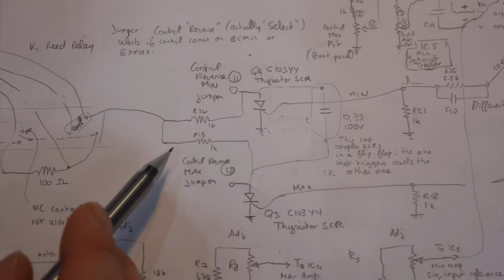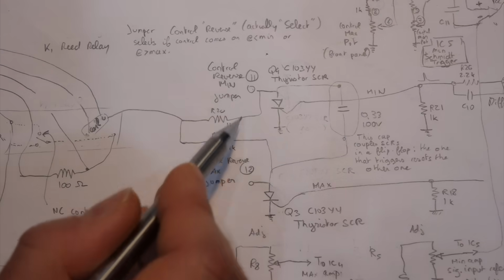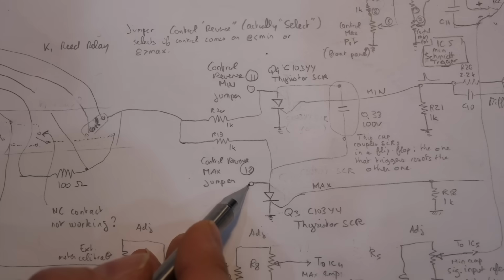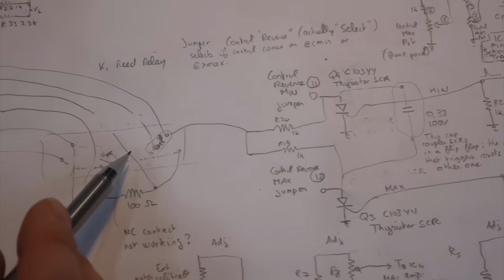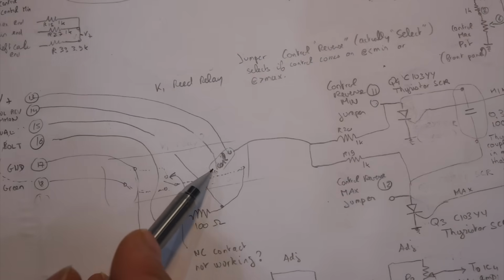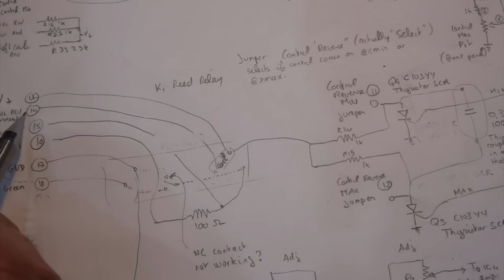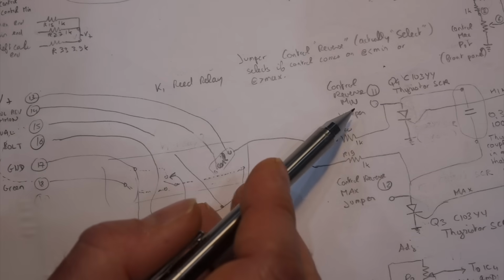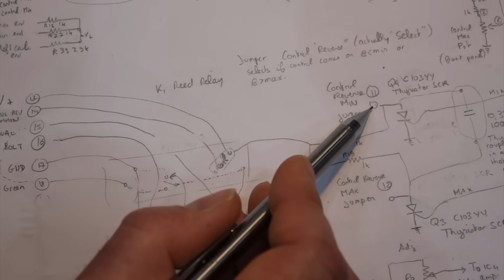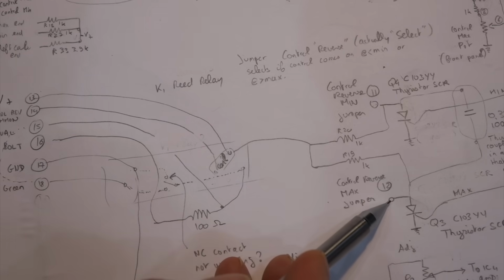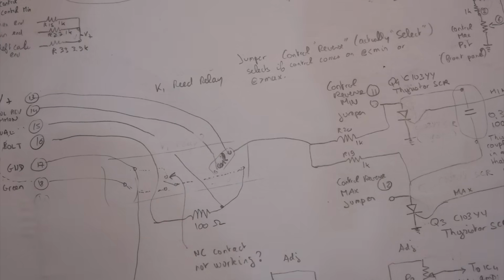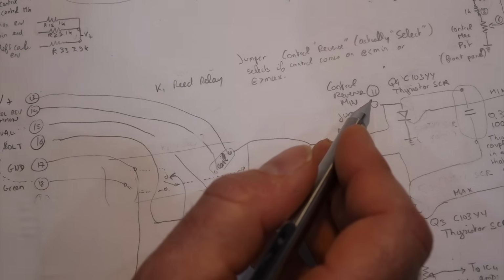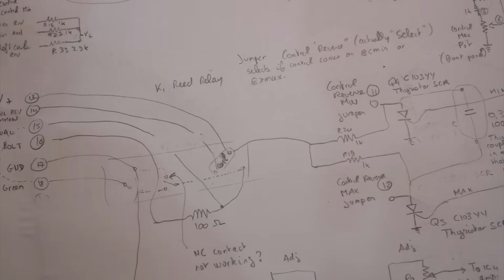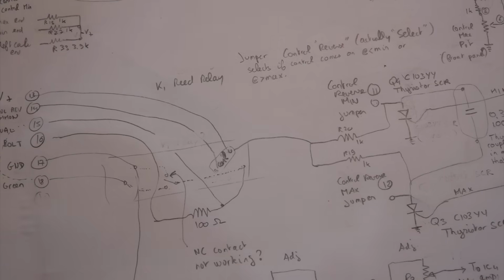And the other subtlety here is that the outputs of the SCRs were connected to nothing. And the other coil of the relay was connected to nothing either. And what happens is that those two need to be connected, and you choose whether this side of the flip-flop or this side of the flip-flop does the control. So you have this control reversal. But if you don't have a connection, it won't work, and that's what was happening to me. I was missing the connection, and that's over here.